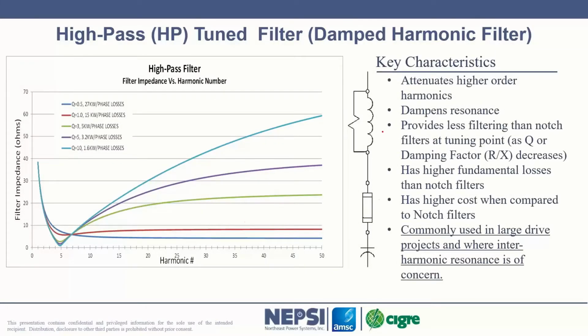A high pass filter is shown here, and we have a value R parallel with the value X, the inductor. And you can see here the impedance curves, filter impedance on the y-axis and harmonic number on the x-axis here. So you can see that by changing the value of R here, we can change the shape of this filter impedance curve. Obviously, if we bring R to infinity, to a very high value of ohms, it's like it doesn't exist, and then it looks like a notch filter. And that's what you see here in a blue curve. Okay, Q of 10 almost looks like a notch filter, right? It has a very similar look to a notch filter.